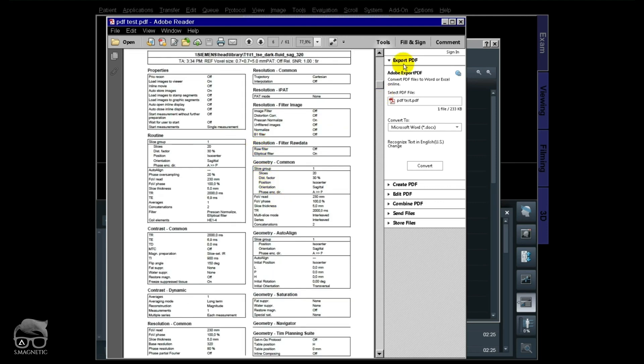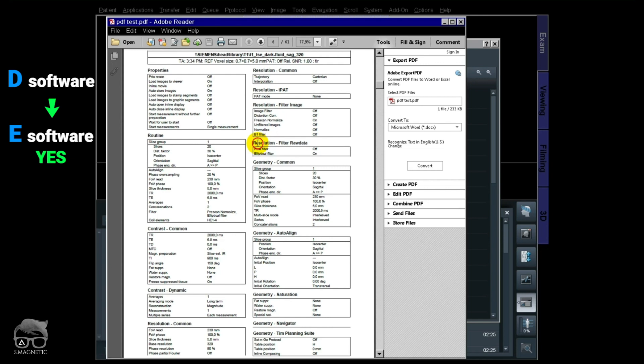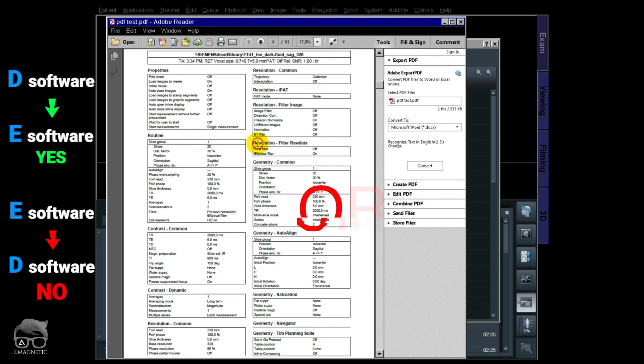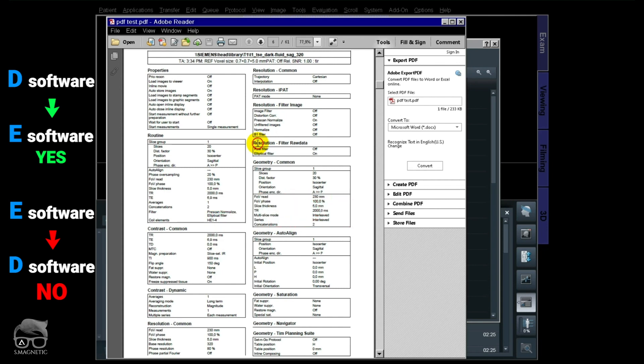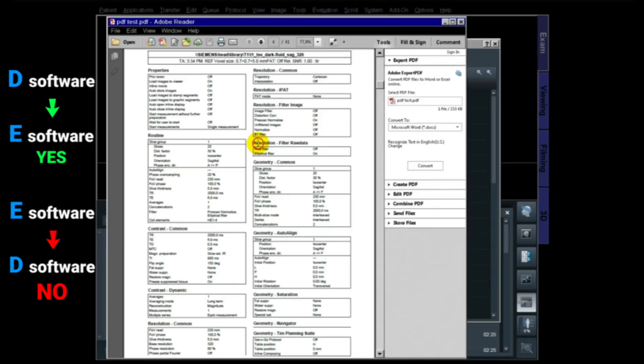So the thing is that if you have software e11c, that means that you can import sequences from the older version. If you have an older version, you cannot import from a new version, vice versa. So whenever you got a fault error message, that means you cannot get the import. So with the PDF file, you can rebuild the sequence. It takes longer time, but possibilities are right there.